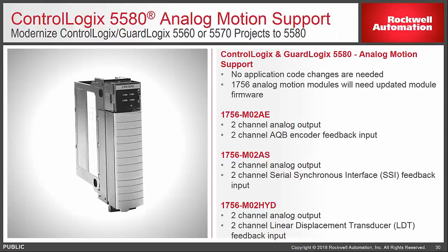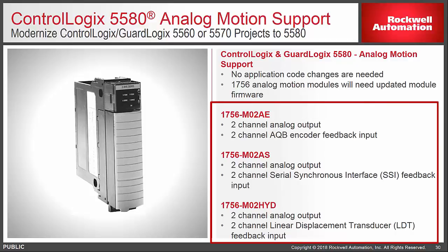As we continue to round out the functionality of the ControlLogix 5580 controller, we will also be adding in version 31 the ability to support the analog motion cards that were available in previous versions of Logix controllers. So the 1756 M02AE, M02AS, and M02 HYD cards will now be available and supported in the 5580 controller platform.